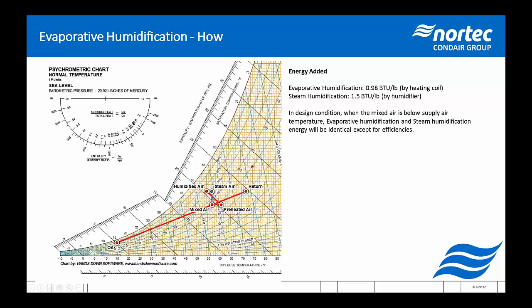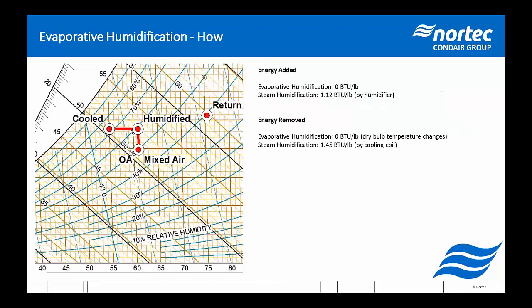However, if you're doing it with an evaporative technology, you have to preheat that air and then cool it back down again. So this is the preheat penalty, and there is absolutely a preheat penalty. And in design condition, you will need to preheat approximately equivalently to what you need to heat for a steam humidifier. However, the vast majority of the time, we're not in design conditions.